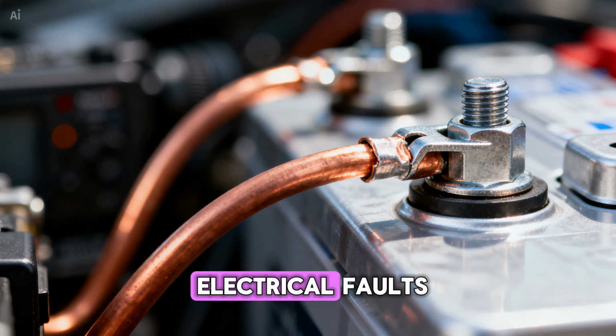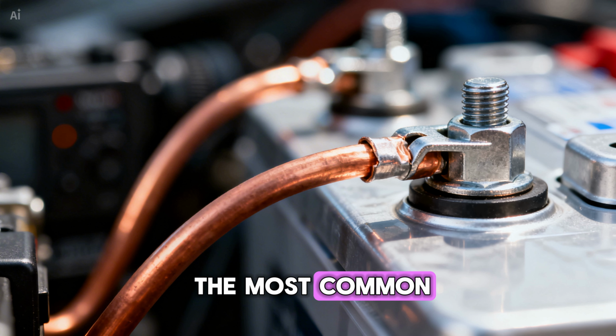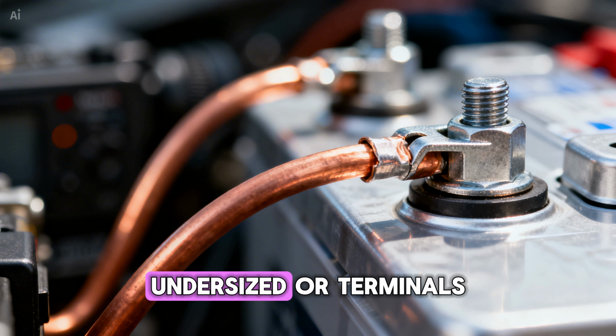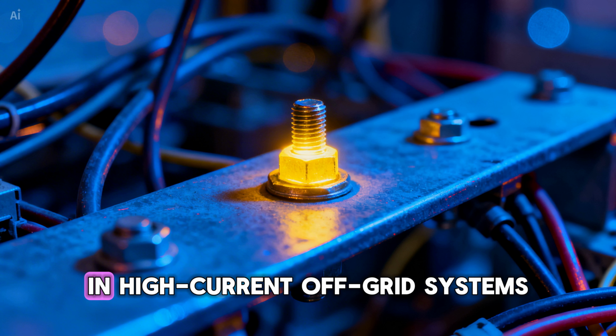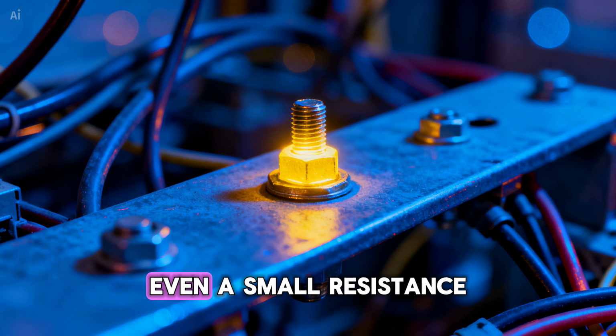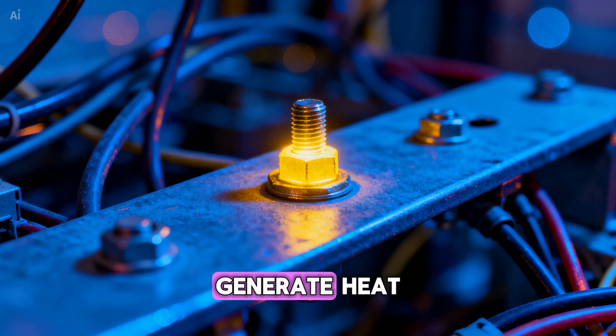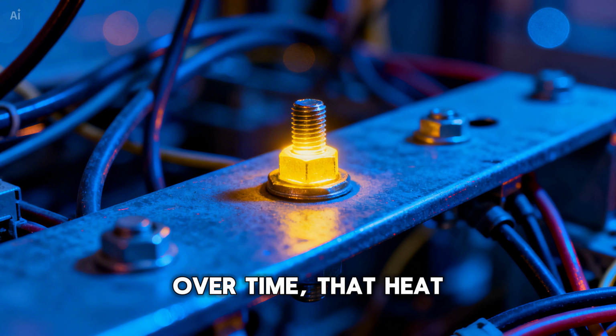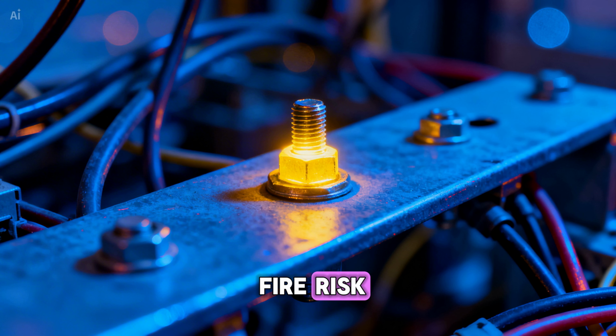Now let's talk about electrical faults, which are one of the most common real-world causes. These happen when wiring is undersized or terminals are loose. In high-current off-grid systems, even a small resistance point can generate heat. Over time, that heat builds up until it becomes a fire risk.